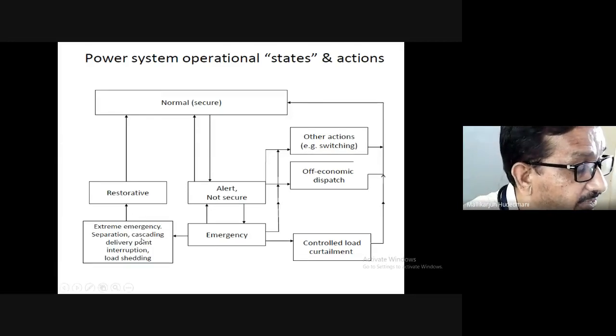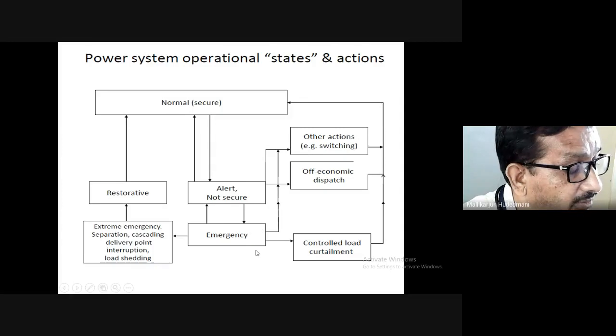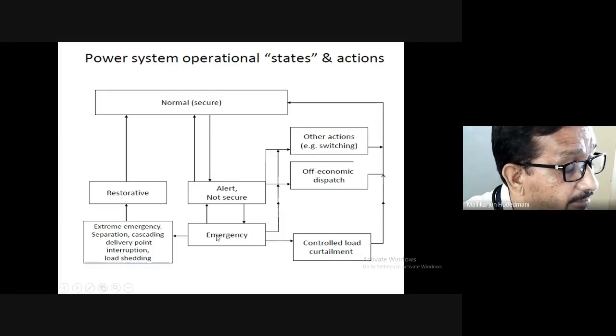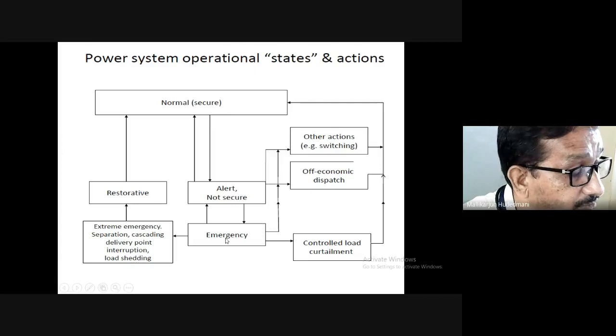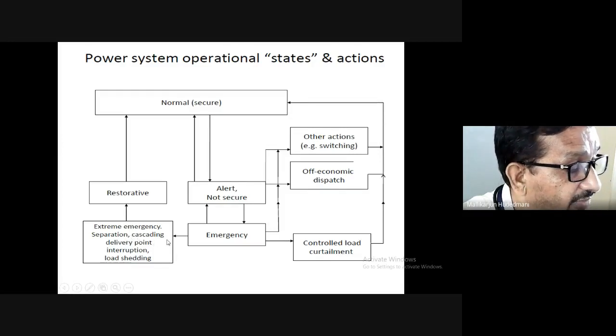Wrong set points, wrong decisions taken during the emergency, which you would have controlled properly, lead to wrong mechanisms and wrong judgments, which result in several component failures in part or in full. This is what we call a cascaded failure, and interruption of delivery is guaranteed.